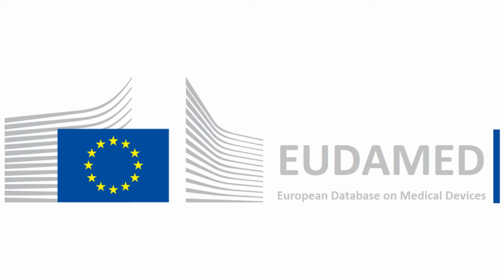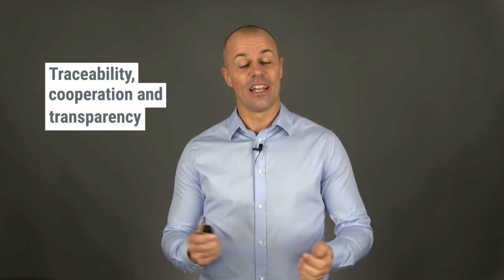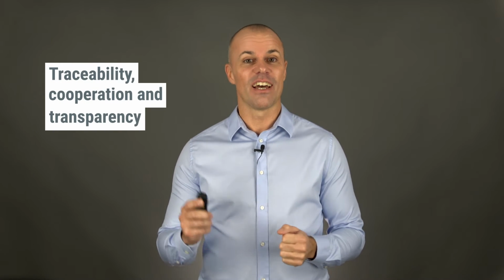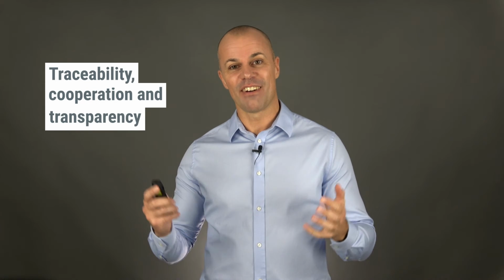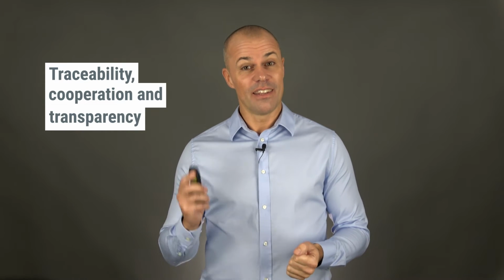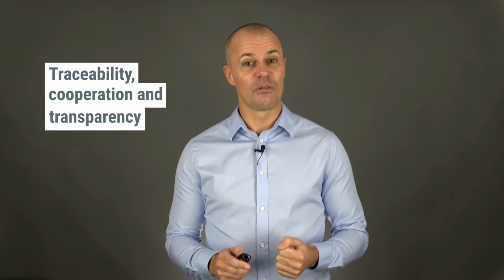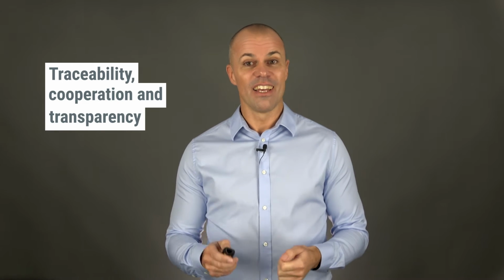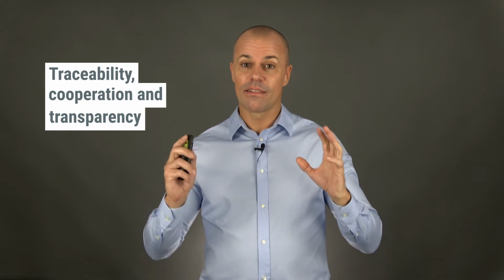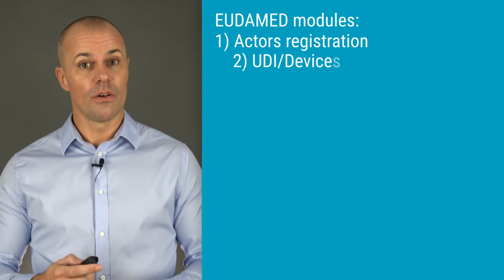But before we do, I want to clarify the purpose of EUDAMED. The main purpose of EUDAMED is to enhance traceability, cooperation and transparency regarding medical devices in EU. The database will be huge considering all data that shall go into it. Therefore, it has been split up in 6 different modules with specific purposes. And here are the 6 different modules. You can also see them in text below this video.